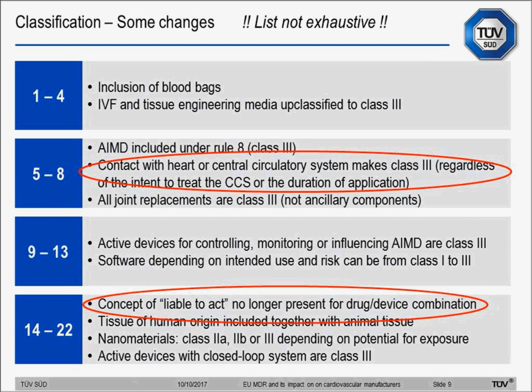So there are quite a few changes and quite a few new rules introduced, but I will focus mostly on those devices that are used in contact with the central circulatory system and those devices that incorporate a medicinal substance. So the three rules that are typically applicable to cardiovascular devices under the directive are Rule 6, 7, and 8. Those are related to surgically invasive and implantable devices. The numbering of the rules will not change in the MDR, so the homologous rules will remain 6, 7, and 8. Rule 8 for implantable devices has no significant changes, while in Rule 6 and 7, some modifications have been introduced that might change the classification of some cardiovascular devices.